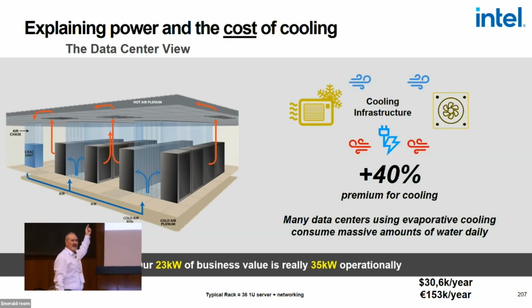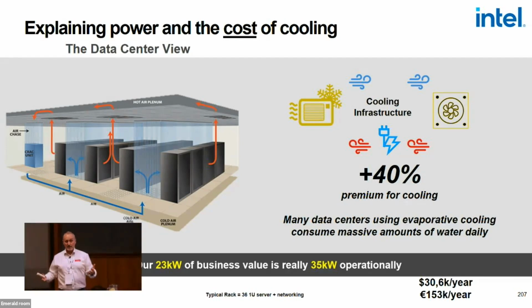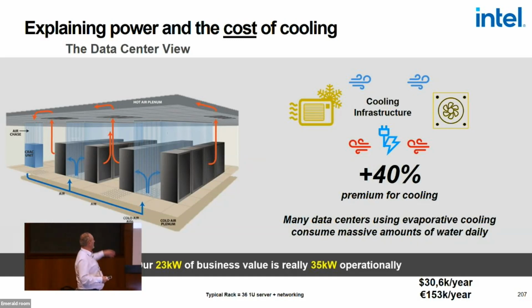So this is what we have now in our data center. One of the things I very often run into when talking to a customer about direct water cooling is that they say, yeah, but we have an old data center and we only have air cooling, we don't have water in the data center. My first question then is: do you have chillers? Do you have chilled air? The answer is yes. Okay, so you have water in your data center, because that air is being cooled by chilling water.